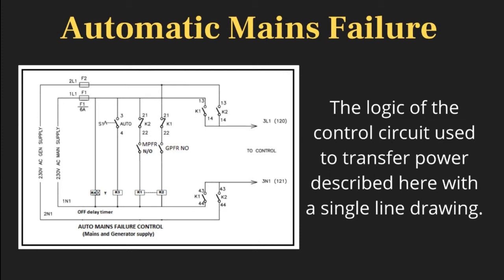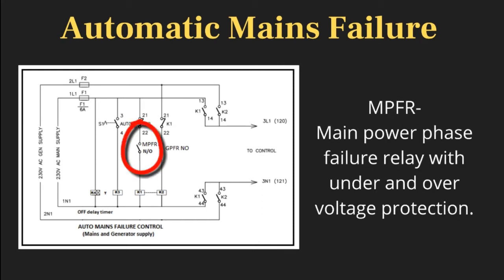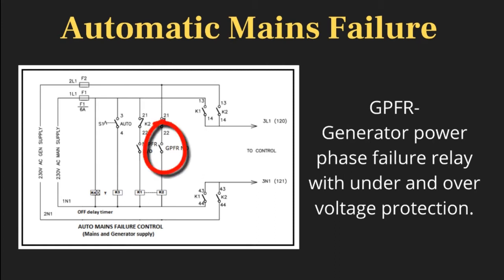The AMF control system is used to transfer power, as described here with a single line drawing. Key components include: MPFR — main power phase failure relay with under and over voltage protection; and GPFR — generator power phase failure relay with under and over voltage protection.